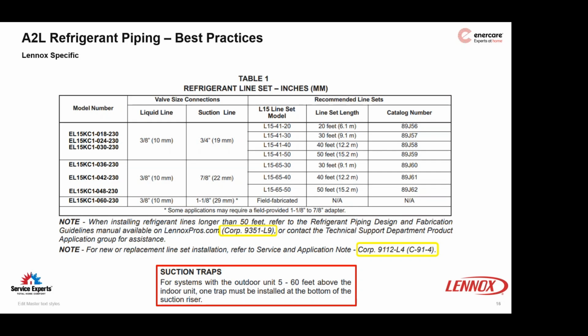If there's more than a 5-foot rise, they're expecting a trap to be installed, basically to ensure that the oil doesn't log out in the indoor unit or at the evaporator. It gets pushed back, entrained within the refrigerant, back to the compressor. And it does so by creating a trap and forcing the oil back with the refrigerant flow.